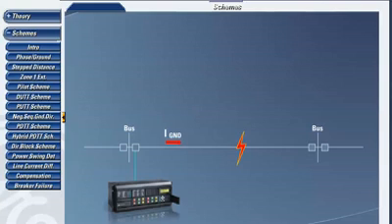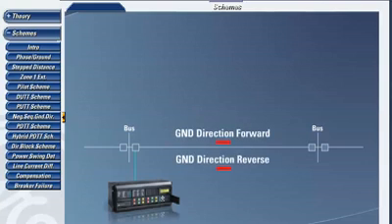The ground directional overcurrent elements let the pilot-aided schemes know if the ground current rises above a minimum set level, and if it does, what direction the ground current is flowing. The ground directional overcurrent elements are used by the pilot-aided schemes because they are sometimes more sensitive to detecting faults than the distance elements are when the source has a weak in-feed or high system impedance ratio.